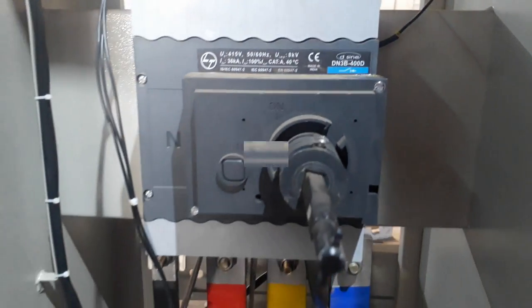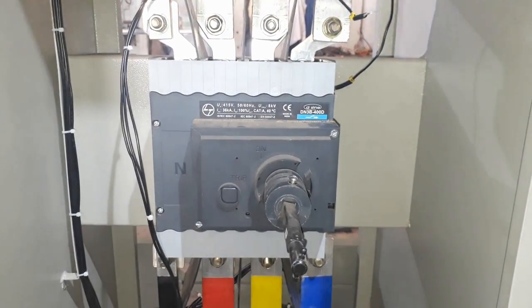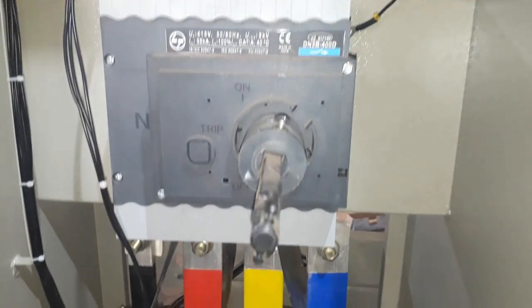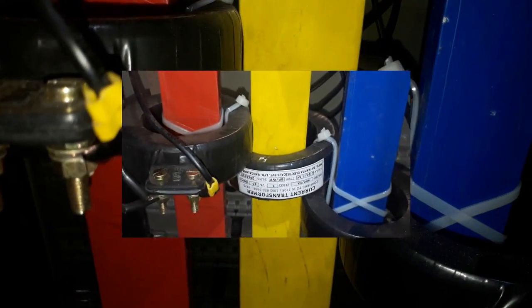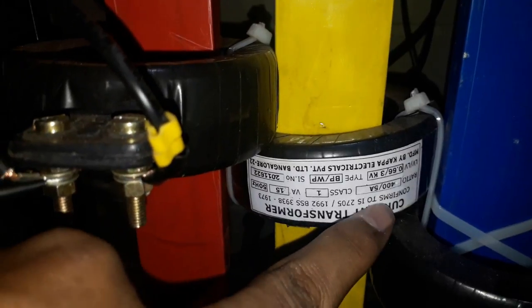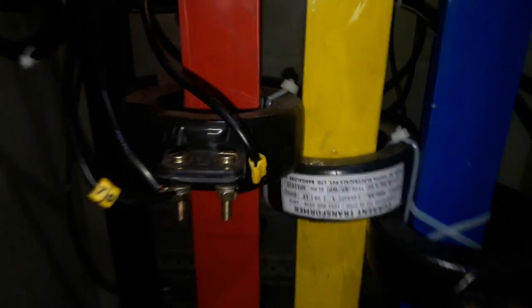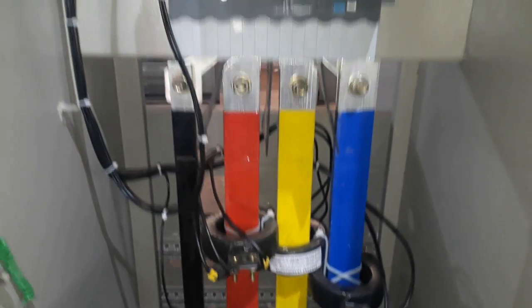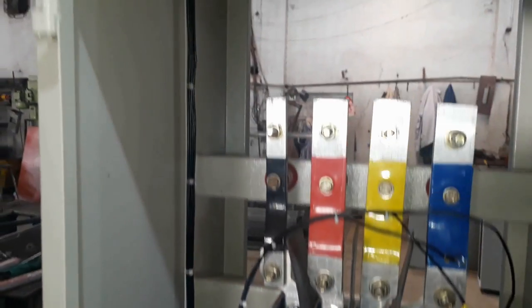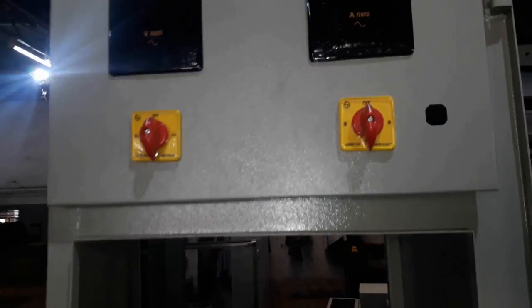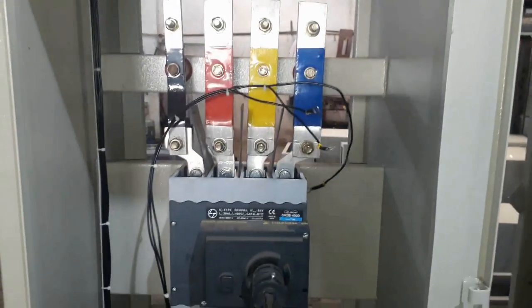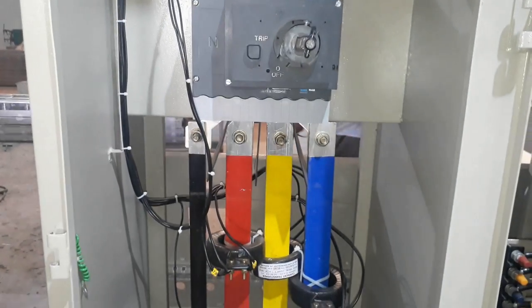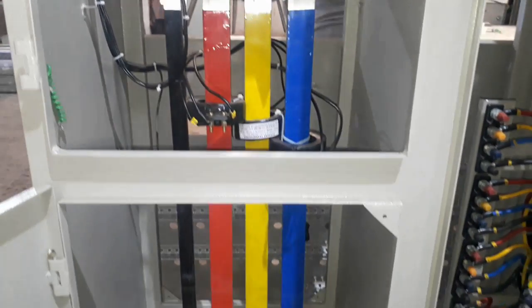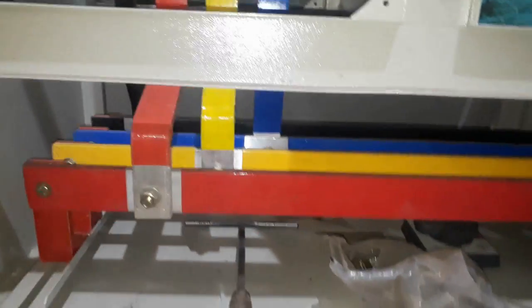As you can see here, this is a 400 ampere main MCCB, and at the output of this MCCB the bus bars are connected, and to these bus bars a CT is connected for ammeter wiring. This CT is required for ammeter wiring. This one is a 400 by 5 ampere class 1 CT. The detailed wiring is shown in the previous video, you can check that video too. So the main MCCB feeds the bus bars, and to the bus bars the CT is connected.